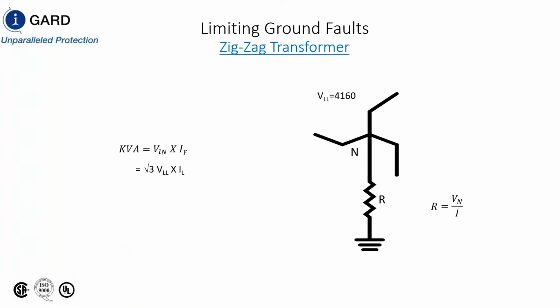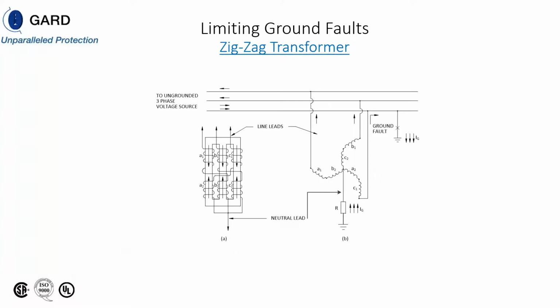So the zigzag transformer is quite unique in that the winding of one phase is wrapped around one leg, and then the winding of another phase is wrapped around the other half in the opposite direction. So there's a net zero flux when you have no fault current. This means that you have a high impedance to normal system voltages. But when you have a ground fault, the zero sequence voltages have a very low impedance, and then you develop this neutral point, and that resistor over here limits the fault current.